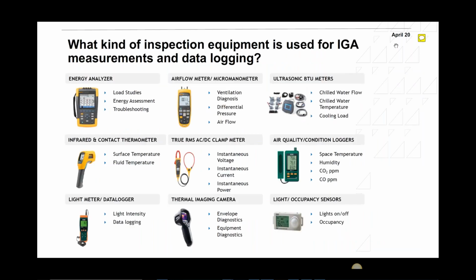Here are some of the data logging and measurement equipment that I normally personally use on site. You can see the energy analyzer, the power analyzer. That's very accurate to get power consumption. Also, it can tell you if any harmonics are on site, and it can show you that through power factor as well. A bit expensive but very useful. An airflow meter checks the flow on, let's say, an air handling unit. It can also show us the differential pressure, let's say, between the indoors and the outdoors. Ultrasonic flow meters coupled with temperature sensors on the supply and return for the chilled water on the chiller show us the BTU meter, or on the main header.